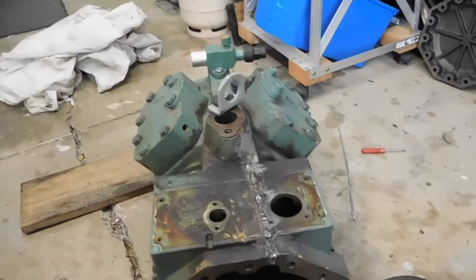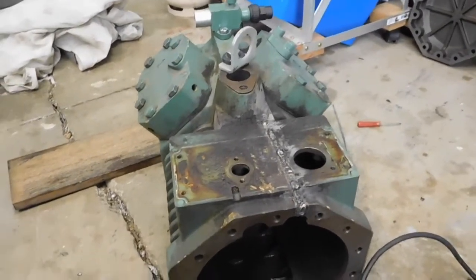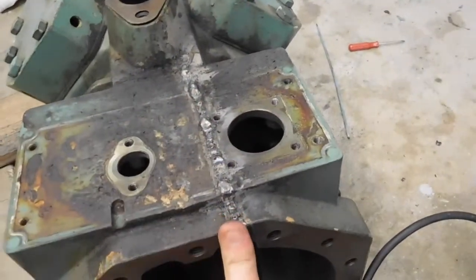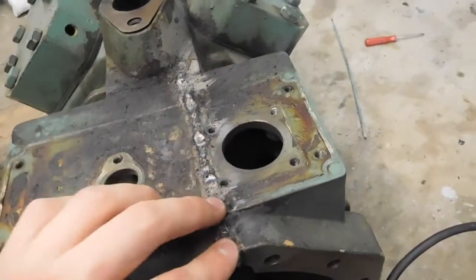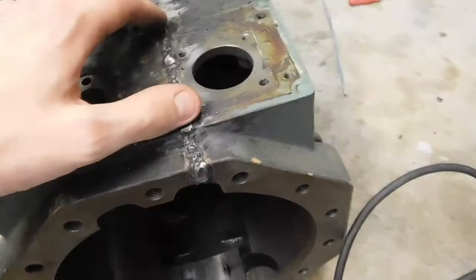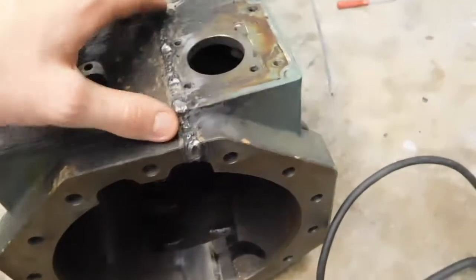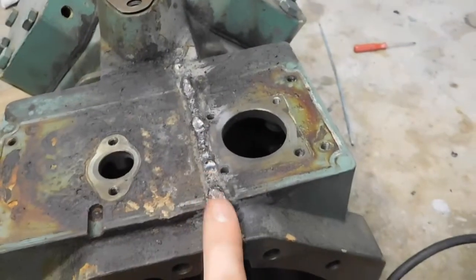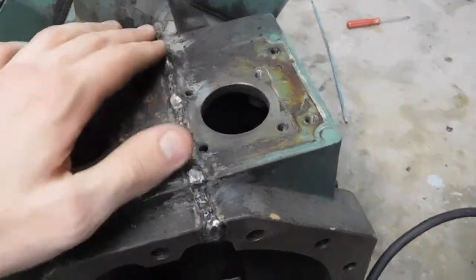G'day everybody, welcome to Part 2 of the four-cylinder Bitsa semi-hermetic compressor conversion. I've just finished welding up the cut in the crankcase — or motor casing actually. As you remember in the previous video, I did have to split that to get the stator out, but given how tightly it was pressed in, just heating it on its own wasn't enough. Using some general purpose mild steel electrodes, I'm really happy with the result — it's welded up really nicely.